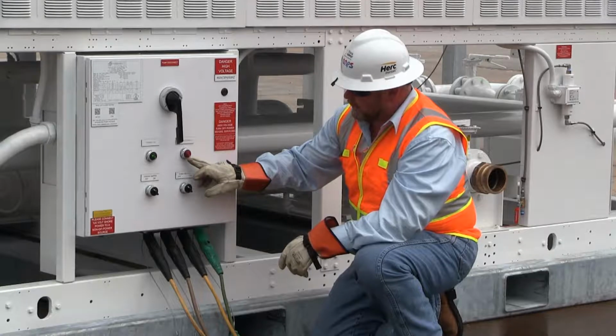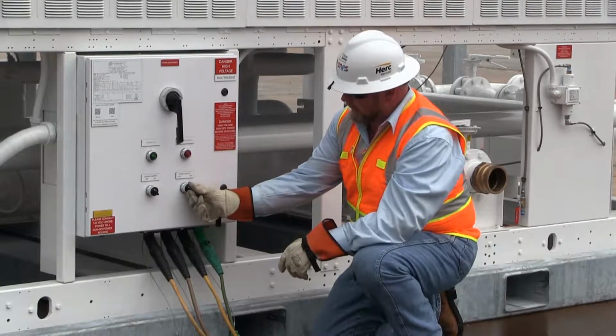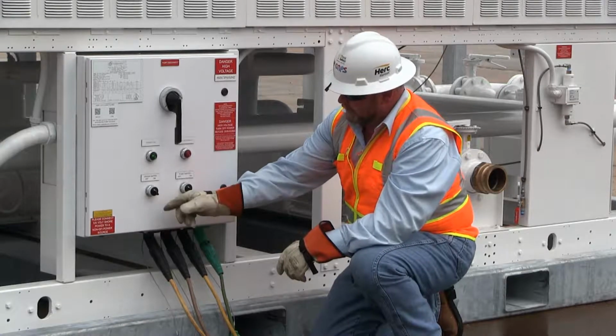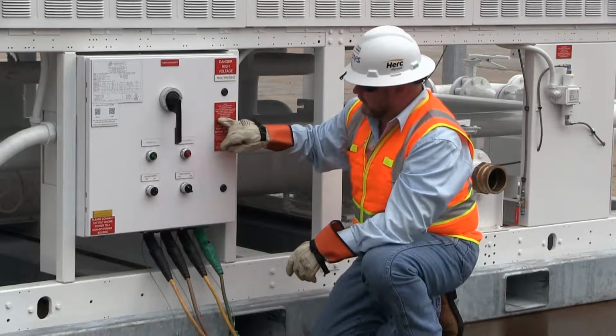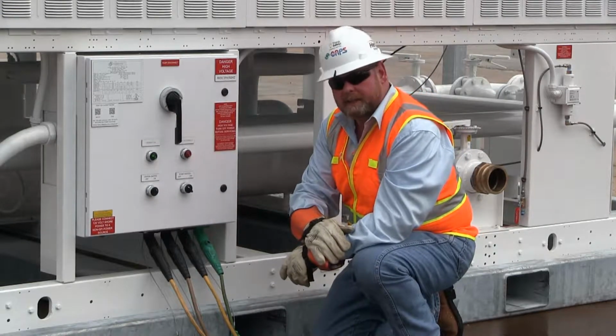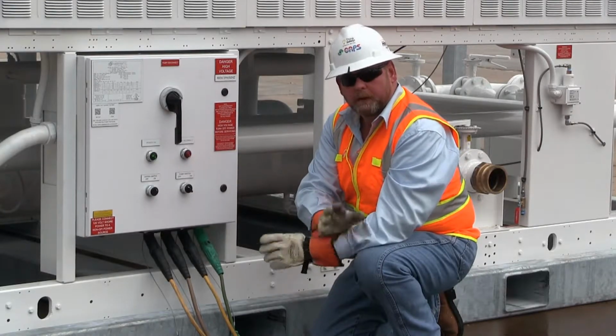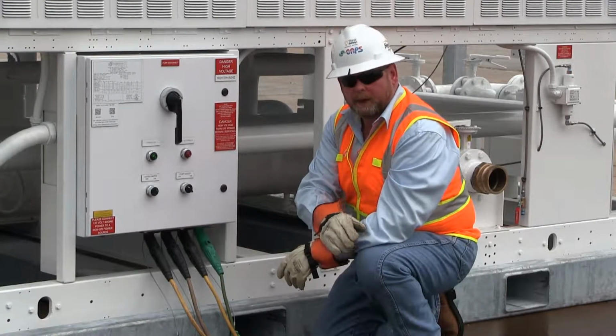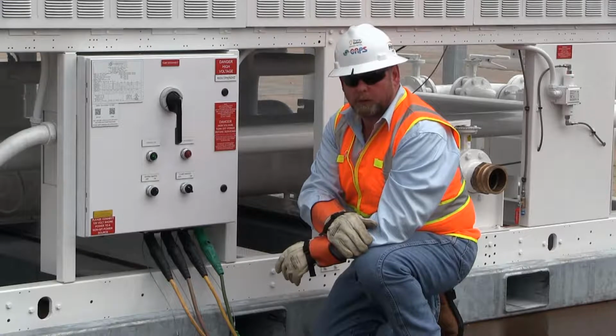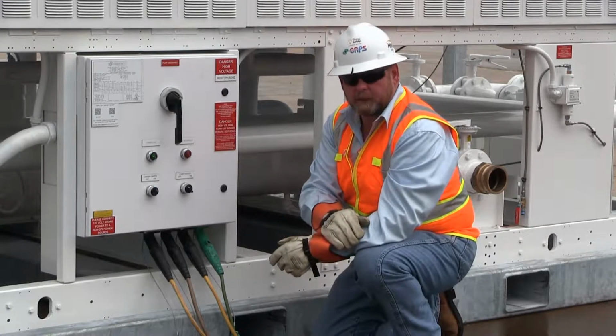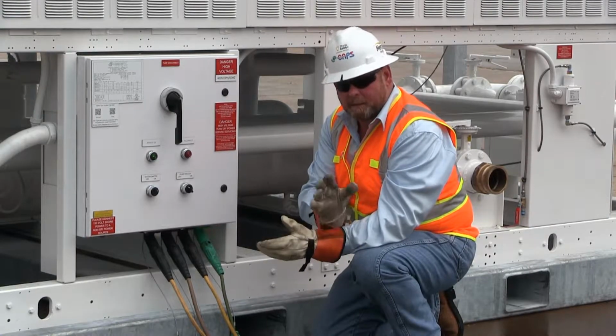Now we have our power light on, the phase incorrect light is off. At this point, this is our master pump switch, our pump breaker, and our main system switch. We're going to turn on our main system switch, and there's a notice here that says that we have a 1 hour lockout timer from the time that you turn the system switch and apply power to the chiller. The purpose of that lockout timer is to preheat the compressor oil and remove any refrigerant that could be trapped in the compressors. This is a manual lockout.